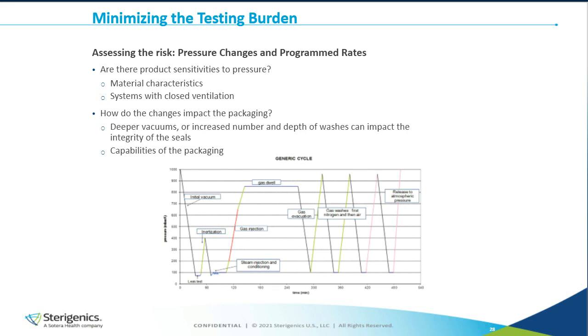If we are talking about pressure and pressure changes, I've been only focusing on the depth of the vacuum, but the rate is also important. If we are pulling a vacuum faster, it can also add more stress on the packaging. So it's important to consider that as well. I would say the closer we can stay to the original cycle, and improve it wherever possible, the more we are going to minimize the testing burden. That's definitely important to consider when a new cycle is being designed.